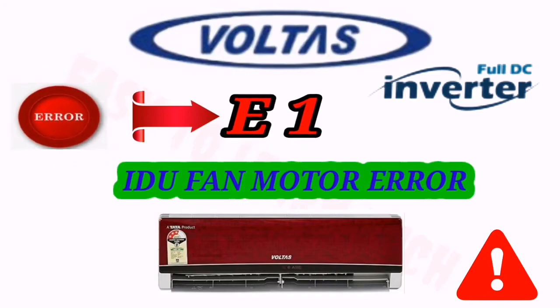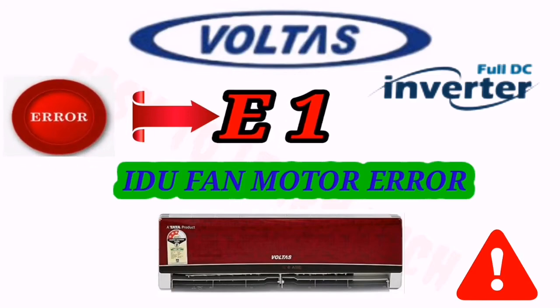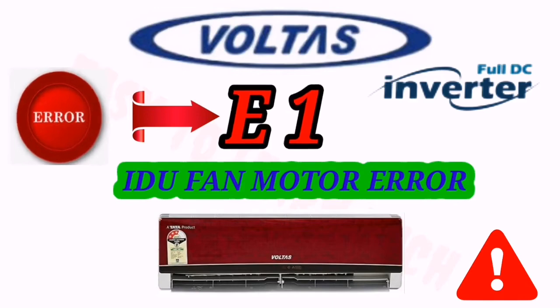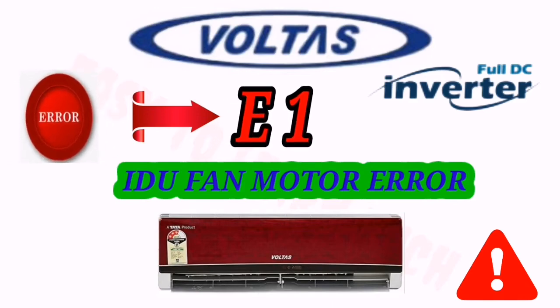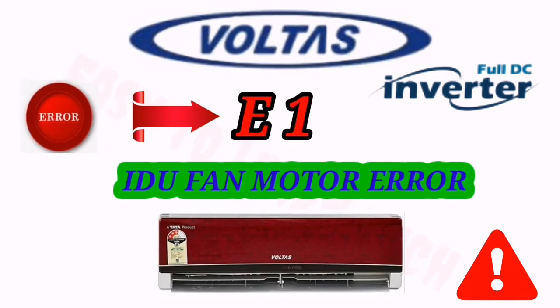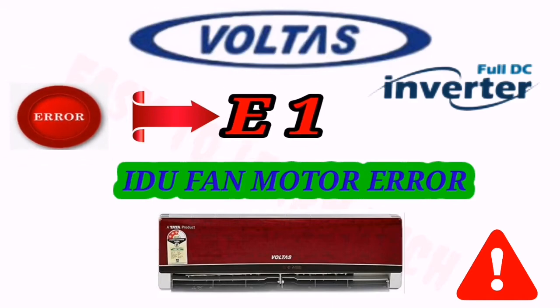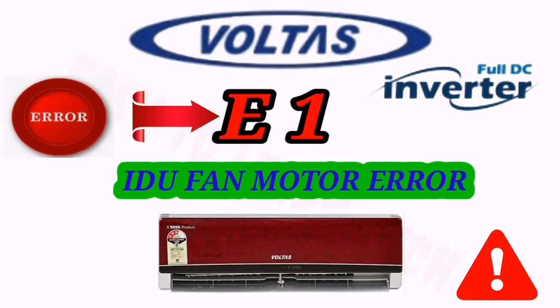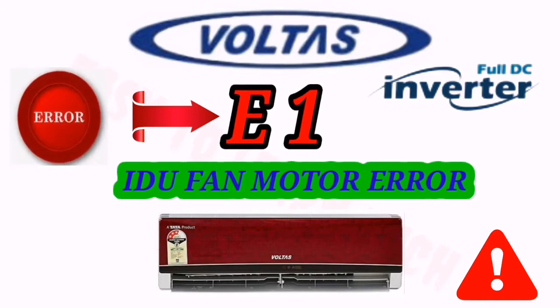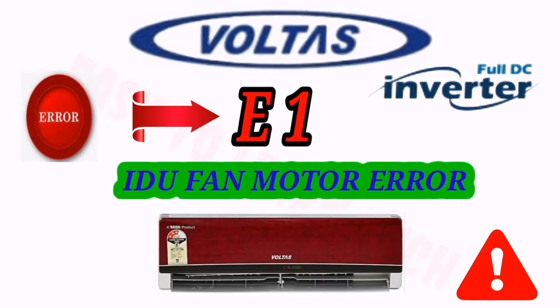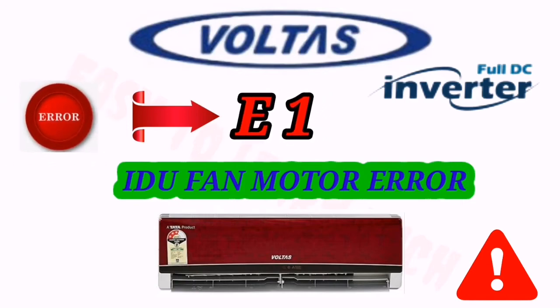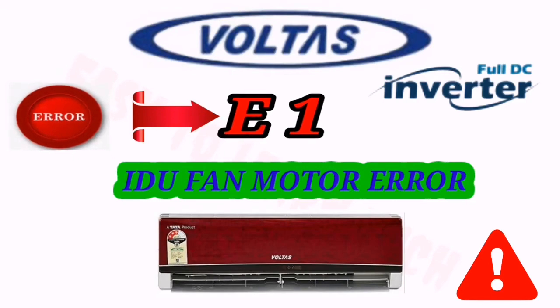In our fan motor, there is one cable that goes from the fan motor to our indoor PCB. It gives the command for the RPM of the fan motor, and on that you have to check that the output coming from the fan motor should be DC 15V. If it is not giving DC 15V, it means the signal from the fan motor is not coming to our indoor PCB. You have to change the fan motor.